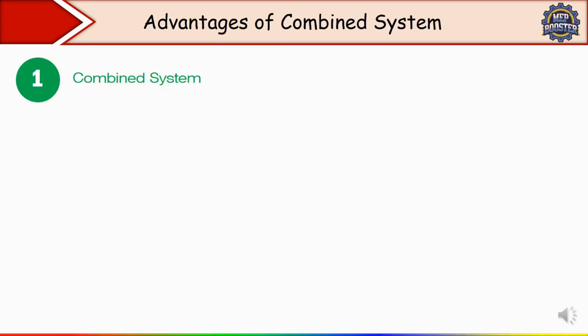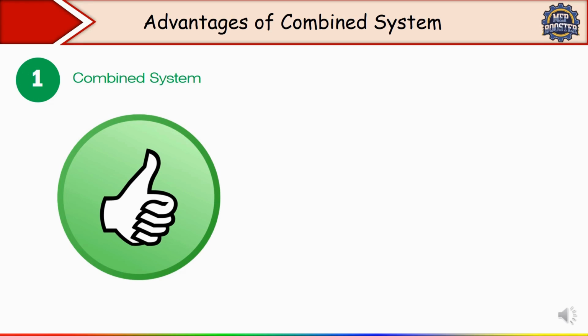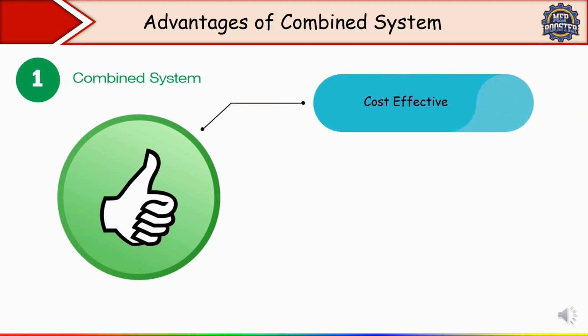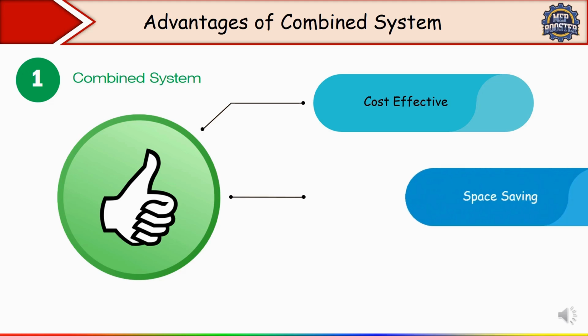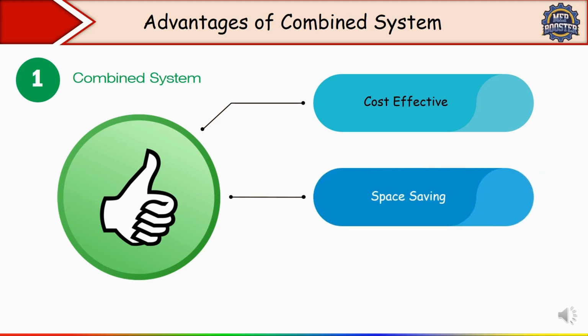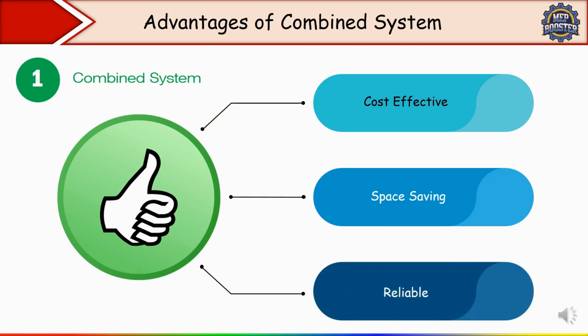Now here some advantages, the benefits of combined system, are given. We have a lot of benefits, a few of which we'll discuss here. The first is cost effective. Remember, a single pump and riser for both sprinkler and standpipes. Here we are using a single pump only for both sprinkler and standpipe, so it is cost effective. Second is space saving, because the combined system reduces the number of pipes and installation area. And then reliable, meaning redundancy from shared water supply and pumping system.